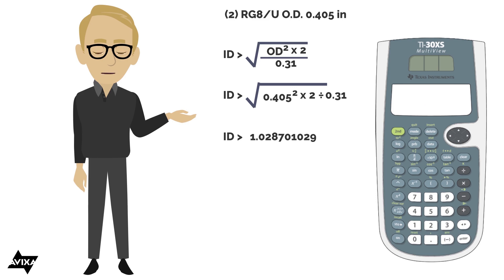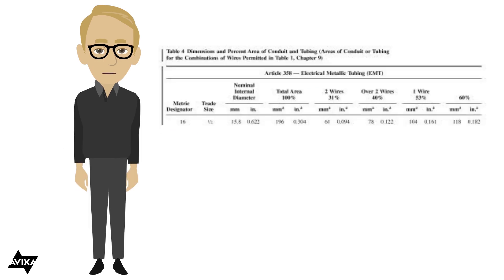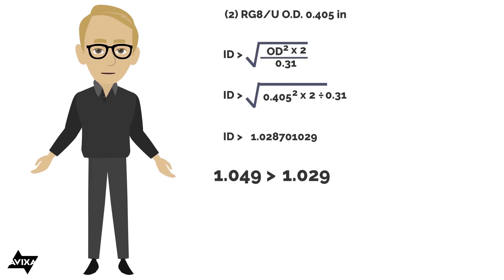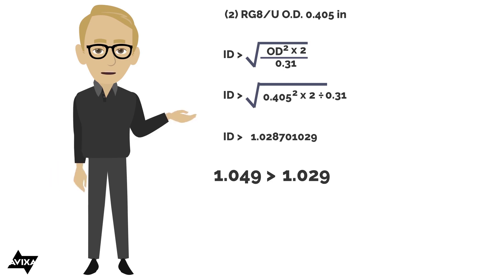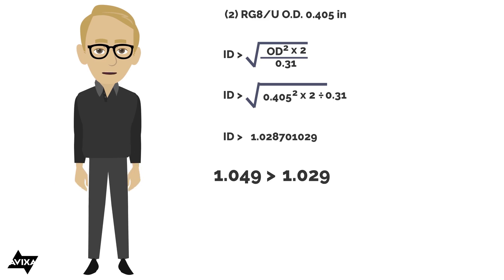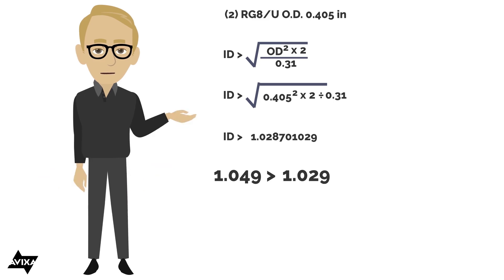So I'm looking for something a little larger than 1.03. Comparing to available conduit sizes: half inch is 0.622 — too small. Three-quarter is 0.824 — still too small. A trade size 1 has an inner diameter of 1.049. Since 1.049 is larger than 1.029, we could use a conduit of trade size 1 in that case.